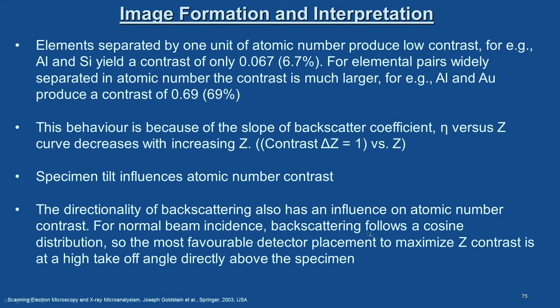For normal beam incidence, backscattering follows a cosine distribution. The most favourable detector placement to maximize Z contrast is at a high takeoff angle directly above the specimen. If you recall the instrumentation details from the lab, the BSE detector is placed just above the specimen, fixed just below the pole piece. That is the position where BSE signals are very well collected. BSE electrons are very high energy electrons, and their trajectories are straight lines compared to the trajectories of low-energy secondary electrons.